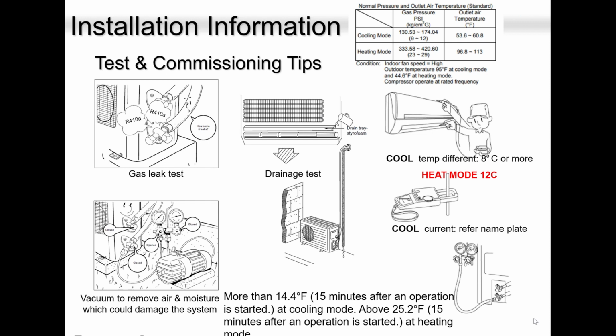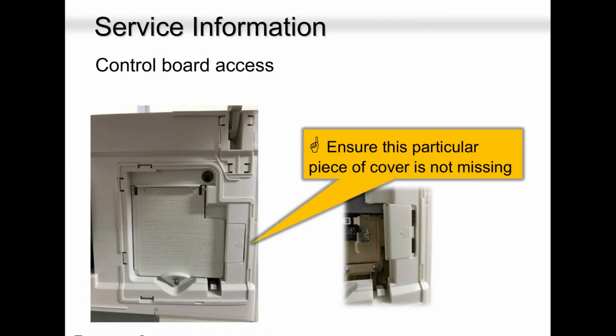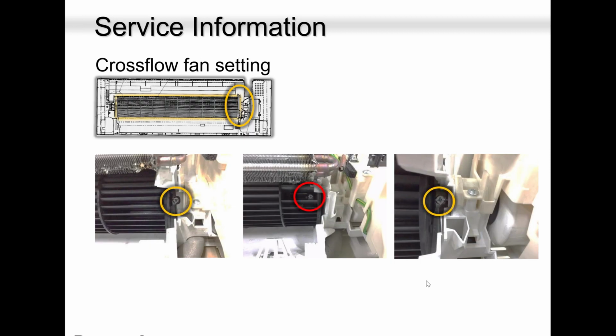Running amps, check your running amps. Everything is good, you leave your job site. This is a picture of your indoor unit. When you open, you will get 3 wires and ground. You can measure your voltages when you have a problem at the indoor unit or at the outer unit. When you want to adjust the blower wheel, or when you want to change the motor for whatever reason, there is a screw there on the right hand side. When you're facing the unit, on the right hand side there is a screw. Open that screw, lift the coil gently, and the blower wheel is out.